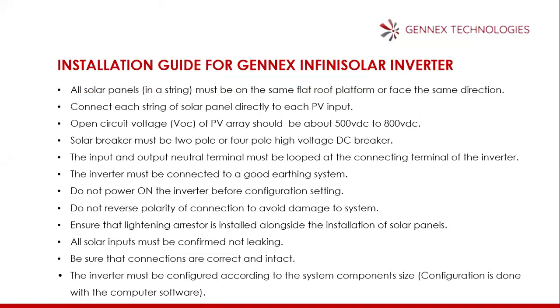Open circuit voltage, which is VOC, of PV array should be about 500 volts DC, 800 volt DC. You can operate within that range. It's safe because the maximum voltage is about 900 to 1000 volts DC. So solar breaker must be 2-pole or 4-pole high voltage DC breaker.